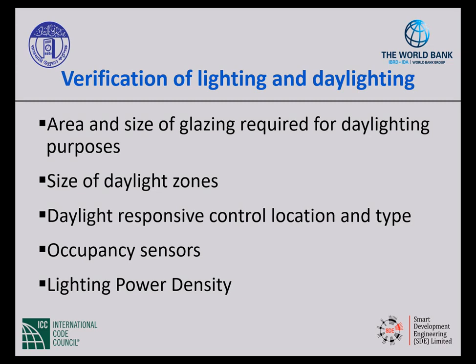The light bulbs are efficient, but shall we shut them off when we don't need them? If I have to choose between lighting power densities and controls, I'm going to go after the controls to make sure that they're shutting them off when they're supposed to. The controls aren't fighting each other. They're in the right places. They're in the right rooms. That there's the ability to turn lights down, dim them, save energy somehow by actually turning them off.